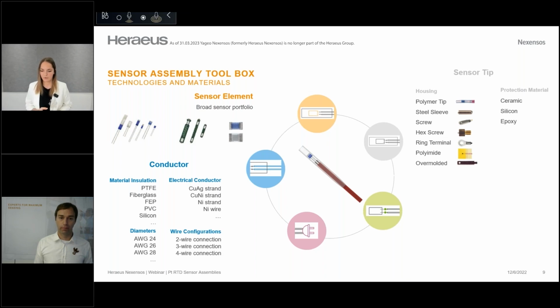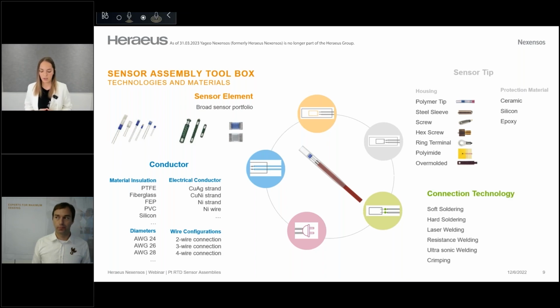Okay, next one. And you will always find a recommendation of the connection technologies on the data sheet of our sensor elements. The recommendation is there because it needs to be matched to the material of the lead wires of the sensor element, and the connection technology also needs to be matched to the application temperature.